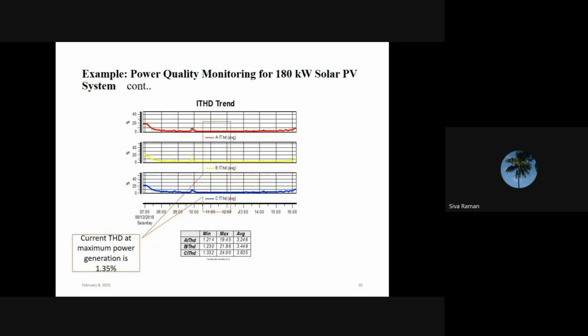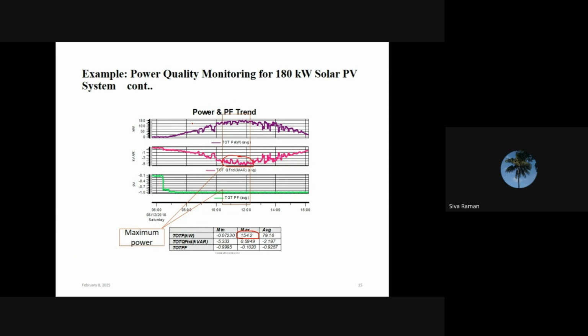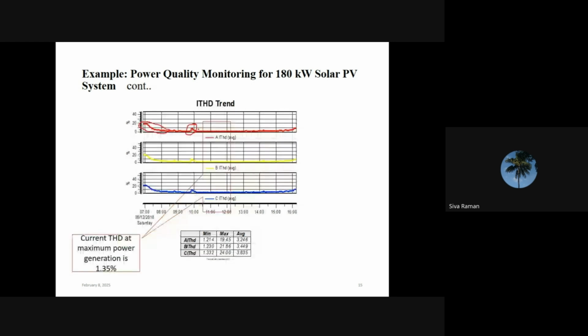Okay, and this one is the current THD. Before the solar generation time, in the R phase, the THD is a little bit high. In this period, around 6 o'clock in the morning, it is around 20%. Slowly it gets reduced when the solar starts generating. Here there is a slight increase in THD, maybe due to the reduction in the power.